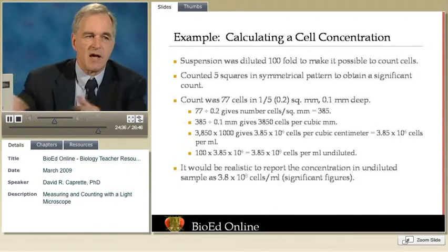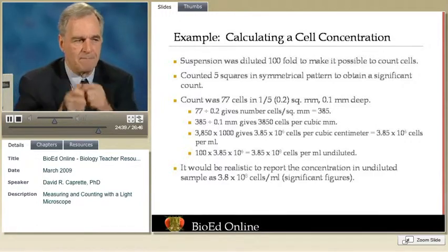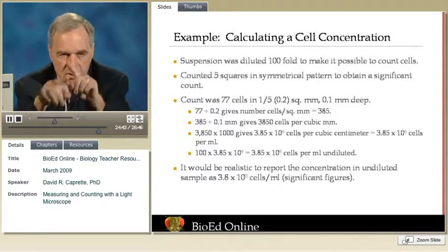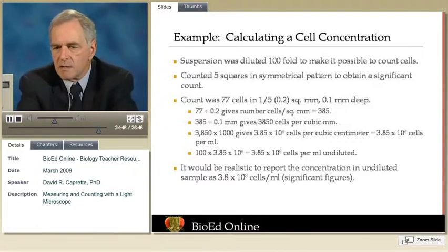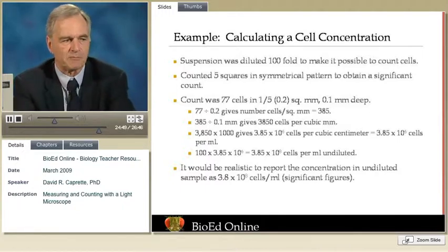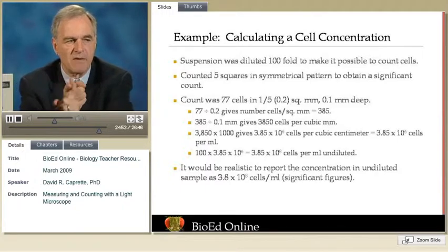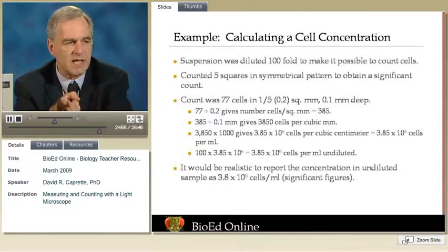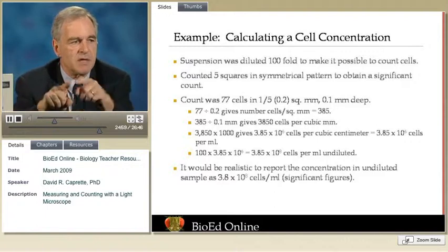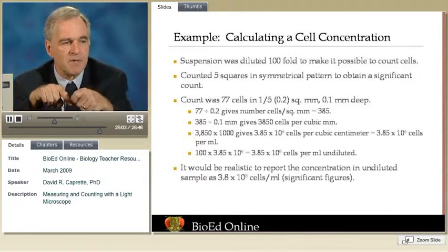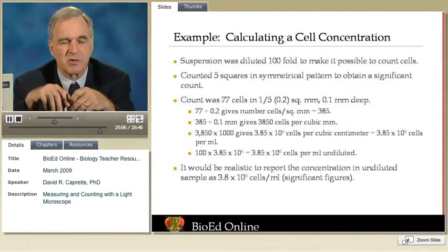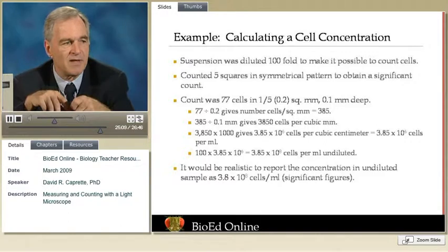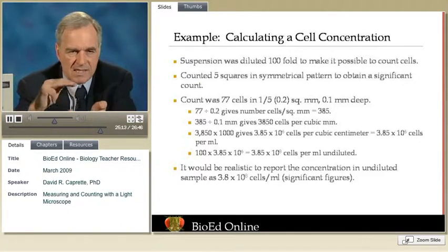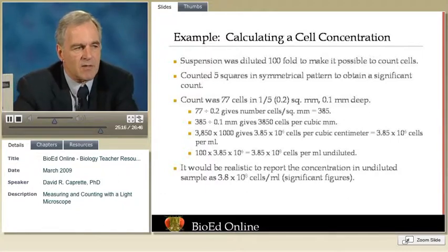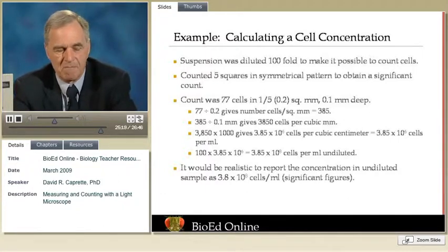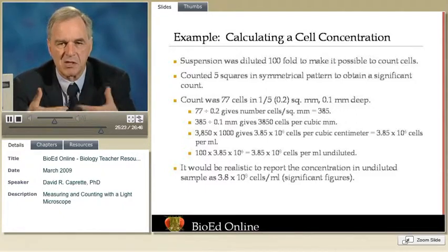Now let's suppose we did count the 5 squares that I talked about in a symmetrical pattern, which is 1/5 of a millimeter squared of area. And let's suppose, as an example, we counted 77 cells. All right, 77 cells in 1/5 of a square millimeter, 1/10 of a millimeter deep, gives us the following result. 77 divided by 0.2 square millimeters gives us 385 cells per square millimeter. Now, if we take that 385 and divide it by 0.1 millimeter, which is the depth of the slide, then we get 3,850 cells per cubic millimeter. And now we have a concentration. We have a number of cells per unit volume.